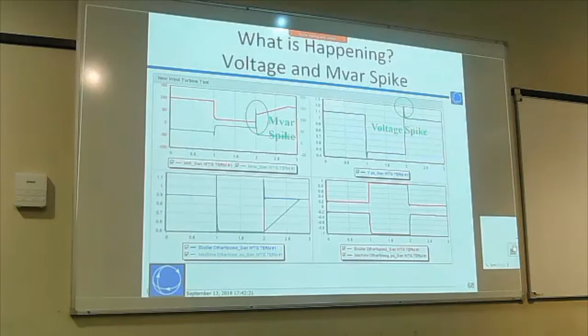So anyway, what we do is, this is what I just talked through. In the simulator, there's a parameter that will say, what is the maximum voltage? And so if you zoom in on that, basically we're just clipping it at that voltage, and we're doing that by just sucking vars out to bring the voltage down. And it happens over about 20 milliseconds.